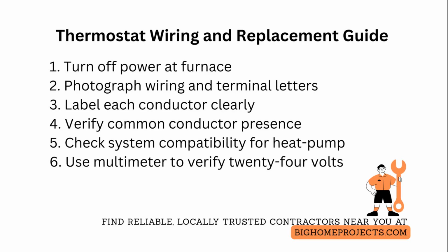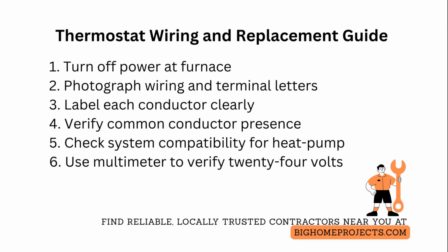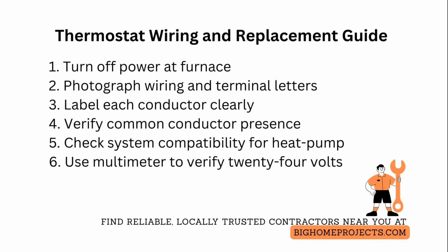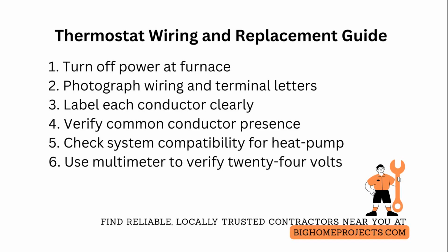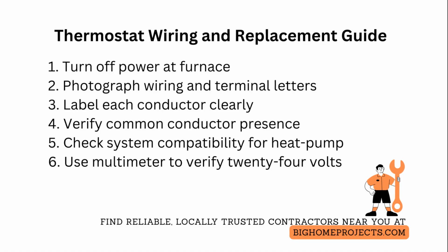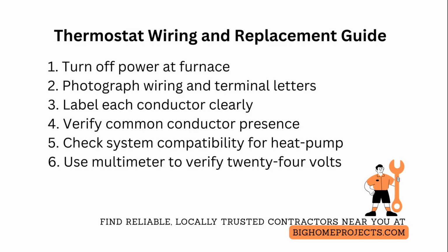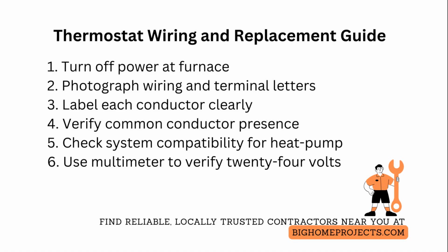And if you lack a C wire, consider battery-powered thermostats, an external 24-volt adapter, or an add-a-wire capacitor kit to create a reliable common. After wiring, restore power and manually force a heat and cool call while watching furnace and air handler response. Check for continuous thermostat calls, like constant fan requests, which indicate a miswired common. Finally, seal the thermostat opening in the wall to prevent drafts that cause false temperature readings and recalibrate the set point to match a standalone accurate thermometer.